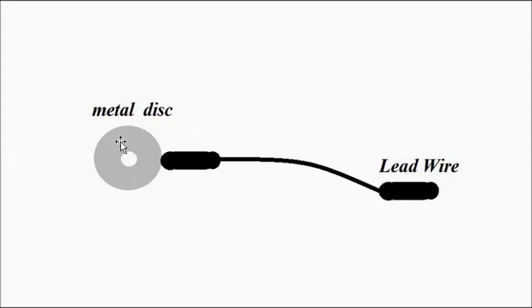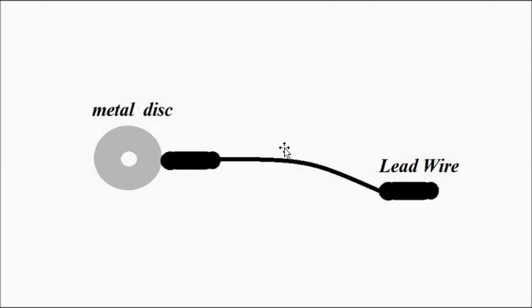The contact impedance of metal disc electrodes is generally of several kilo ohms. The metallic disc is placed on the scalp with the help of suitable electrode paste or jelly so that it does not touch the scalp directly, avoiding the effects of motion artifacts. Lead wires connected to it carry the potential and feed it to the signal conditioning and processing circuitry for amplification, noise removal, linearization, and other purposes.